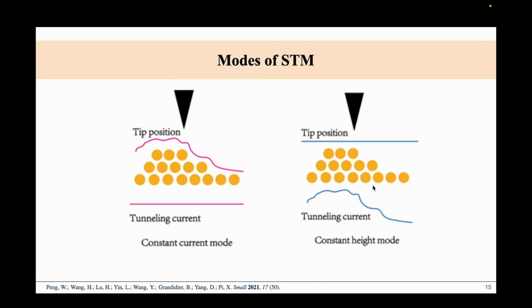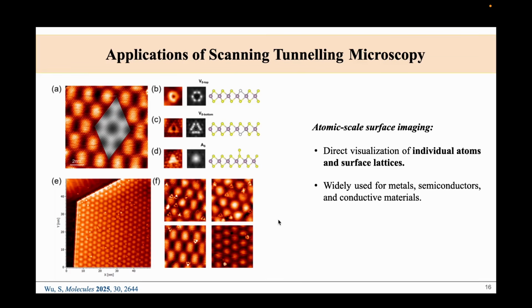On the right we have the constant height mode, and in that case the height of the tip stays fixed and the tunneling current changes as different surface features move under the tip. So here the current variation itself contains the surface information. The constant current mode is usually the more common one because it is safer and more suitable for rough or uneven surfaces. Now let us see some applications of STM. The first one would be atomic scale surface imaging.